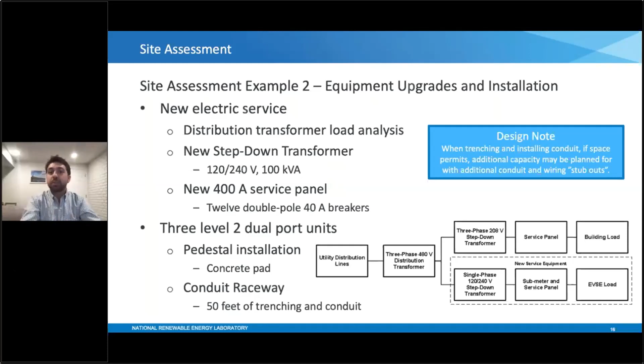Something else you can see here is that we recommend a new 400 amp service panel with 12 double pole 40 amp breakers, or at least the capacity for that many, because this facility in particular was looking at potential future growth. They had even additional parking spaces below the previous image that we had highlighted, where they could plan on installing new EVSE. And right now, because they're going through the trenching costs and the upgrade requirements, it's best to plan for the future. They most likely don't need to install all of the EVSE units, but at least ensuring that you have the spare capacity, and potentially even installing something like the conduit stub out and different wiring options that would make that installation easy in the future, is a great approach. It really saves on the total construction costs in the long term if you think ahead a little bit.